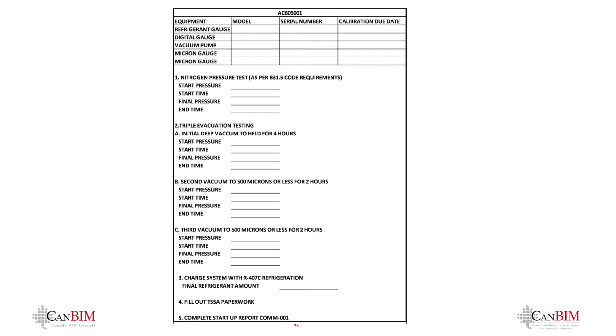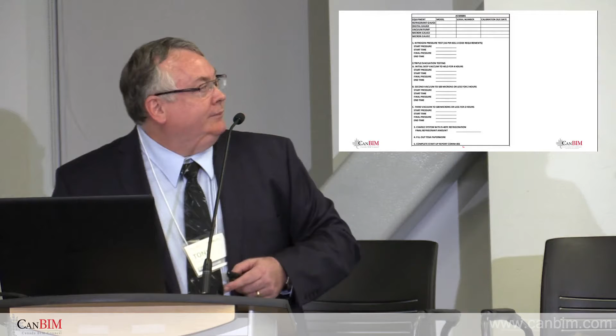Now, with refrigeration systems, there's always a great debate: how do you do the evacuation? Do you pull one really good deep vacuum, or do you do what we like, a triple evac? Instead of being subjective, we define what we're going to do, how long we're going to do it, and what counts as success, and we document it. In the end, it says fill out the TSSA paperwork, which is the jurisdiction having authority.